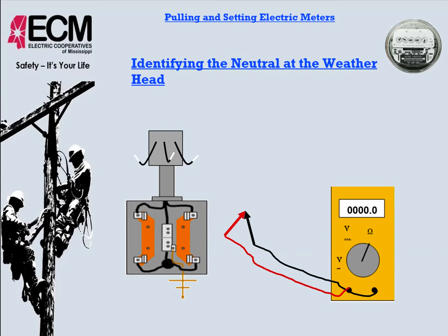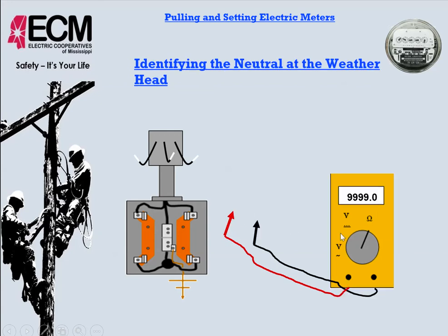Okay, so we need to test our meter to make sure that it is working properly. So we want to touch our leads together here, and now we would have continuity, which would be 0 ohms of resistance, so that we know that our meter's working. If the meter leads are separated, we have an infinite amount of resistance because there's no continuity between the leads. And if we touch them together, it's going to be 0 ohms of resistance. A lot of meters will beep when there's continuity, where there's no resistance. So we're going to be sure the meter's working.